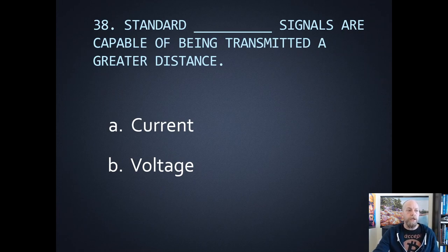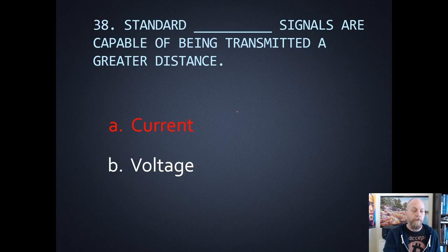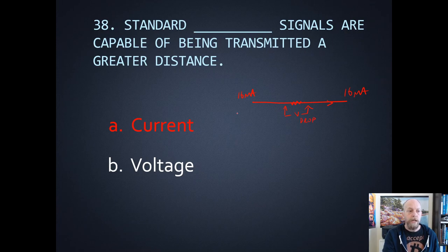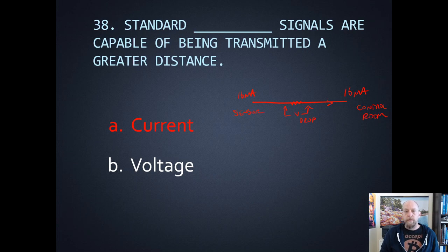Number thirty-eight: standard current or voltage signals — which is capable of being transmitted a greater distance? The current signal is the one that goes longer. On a 4 to 20 milliamp signal you have a series circuit — if you have 16 milliamps at the beginning, you're going to have 16 milliamps at the end. There's resistance and a voltage drop on the wire, but current remains the same in a series circuit. With a voltage signal, you'd have a voltage drop from the sensor to the control room that would affect the signal. So the 4 to 20 current can do 500 to 1,000 feet as long as the power supply is large enough.